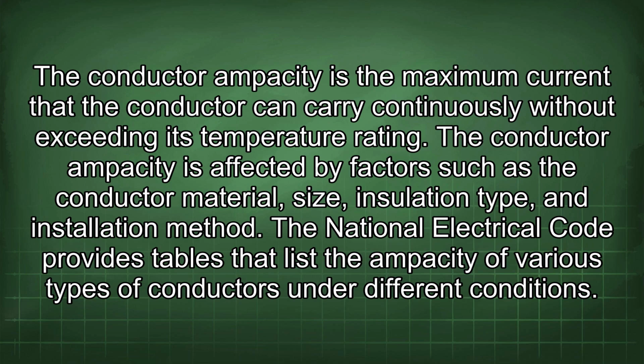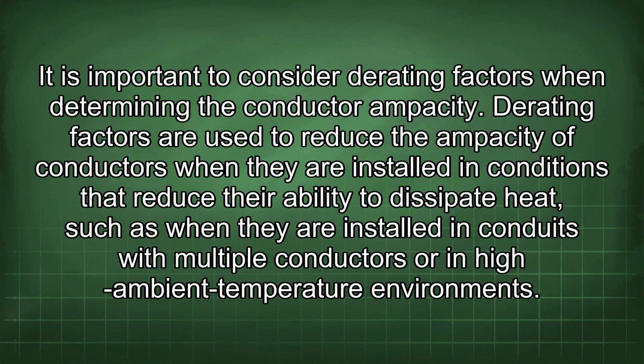The National Electrical Code provides tables that list the ampacity of various types of conductors under different conditions. It is important to consider derating factors when determining the conductor ampacity. Derating factors are used to reduce the ampacity of conductors when they are installed in conditions that reduce their ability to dissipate heat, such as when they are installed in conduits with multiple conductors or in high ambient temperature environments.